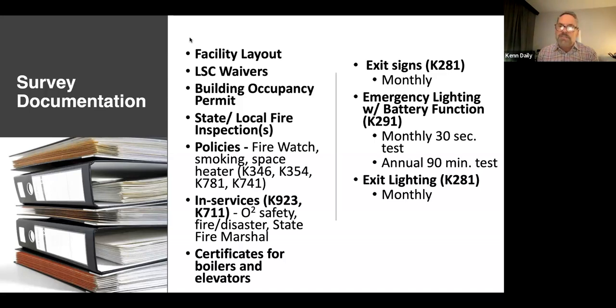I was in a building outside Pittsburgh a couple summers ago. We ran this test for the maintenance, and so we found that 13 of 14 light bulbs were burned out. So again, you need to make sure that you have two fixtures with one light bulb each, or one fixture with two light bulbs, but they can't be on an on and off switch. It can't be on a light meter switch or a sun meter switch. It has to burn, period, when the generator is running, if your emergency lighting is on the generator.